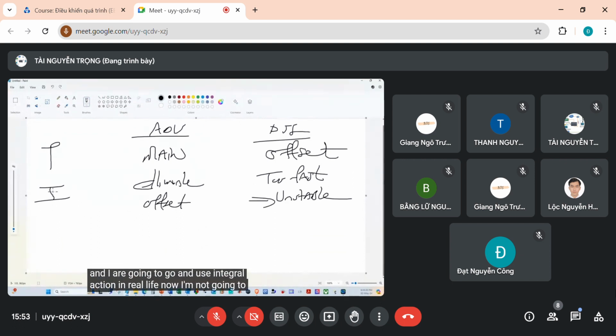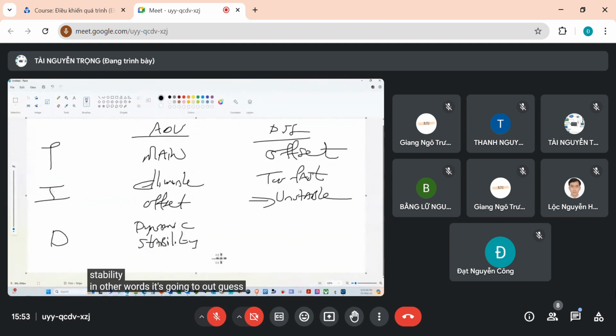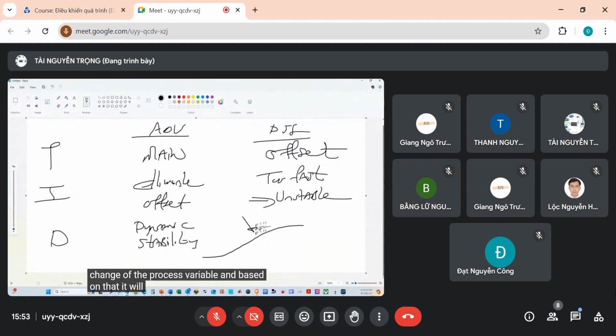Now, I'm not going to have the time to demonstrate derivative action for you, but derivative action is a very intelligent form of control. What it does is it provides us with dynamic stability. In other words, it's going to outguess the process. It looks at the rate of change of the process variable, and based on that, it will open or close the valve quicker to get the process more stable. That's what derivative action does.